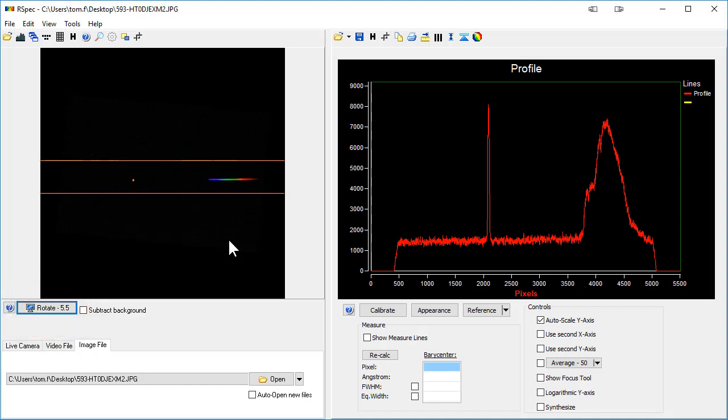In the long run, it's a good idea to get your grating screwed in so that you don't need to use the rotate command, because on some rare occasions, rotation can introduce some minor artifacts in your spectrum. But this isn't a critical issue. For now, just leave the grating oriented the way you've got it and use the rotate features in the software. Then over time, if you feel the need, you can fix the rotation in the grating rather than in software.